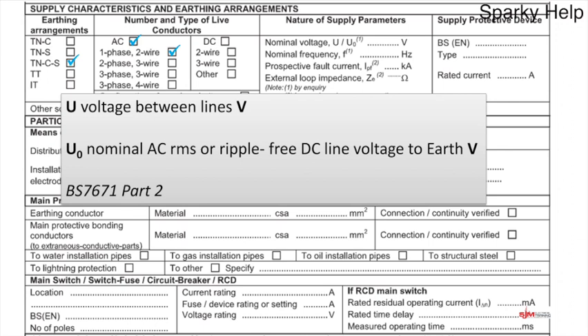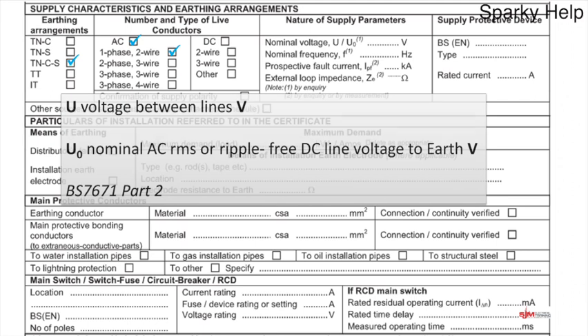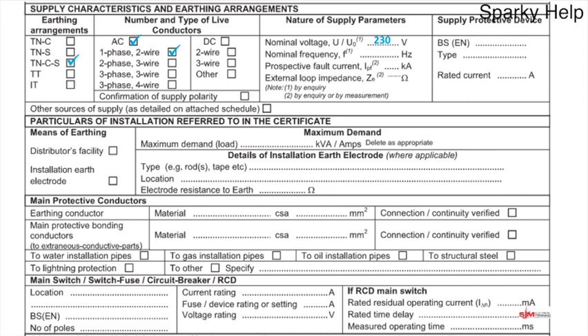U from Part 2 of BS 7671 means voltage between lines, and obviously that's measured in volts. U0 is a nominal AC RMS or ripple-free DC line voltage to earth. So it's a line to earth voltage. So in a single phase installation, that would typically be, for the UK market, 230 volts. A 3 phase installation, yep, you guessed it, U0 would still be 230 volts because it's a line to earth. So if it was a 3 phase installation, what you'd be writing would be 400/230, but ours isn't, as it is a single phase installation, so all we're going to write is 230.